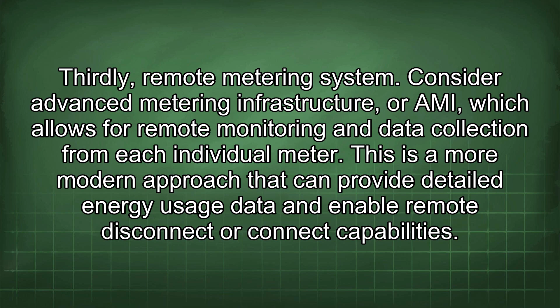Secondly, a centralized meter pedestal. In this setup, a central pedestal can be installed outside, with each condo's meter mounted on it, similar to a commercial meter panel. This consolidates all the meters into one location, which can simplify reading and maintenance. Thirdly, remote metering system. Consider advanced metering infrastructure, or AMI, which allows for remote monitoring and data collection from each individual meter.